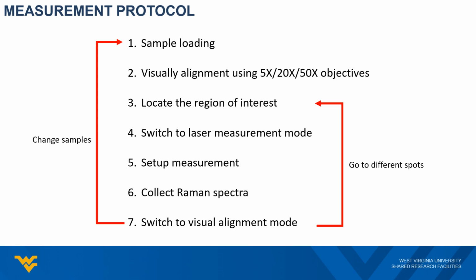Once you locate the region of interest, rotate the 2 big thumb wheels as instructed earlier to change the system from visual alignment mode to Raman measurement mode. Then set up the measurement using software and collect spectra. Once you finish the measurement, you could switch the system back to the alignment mode, then either go to a different spot from the same sample or change to a different sample.